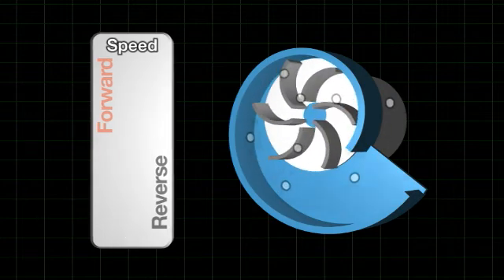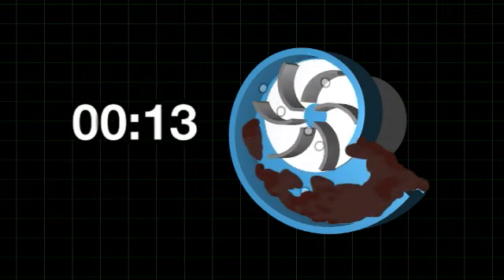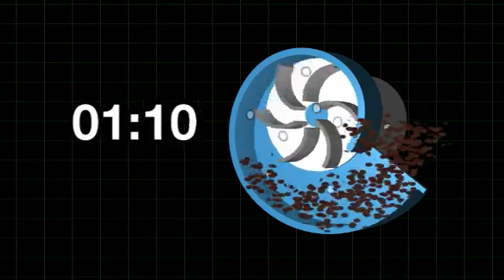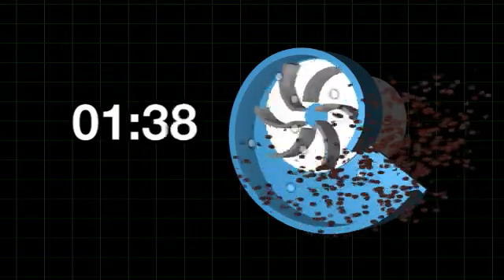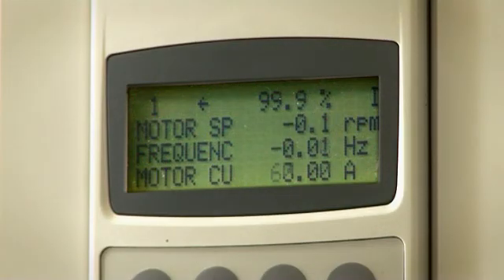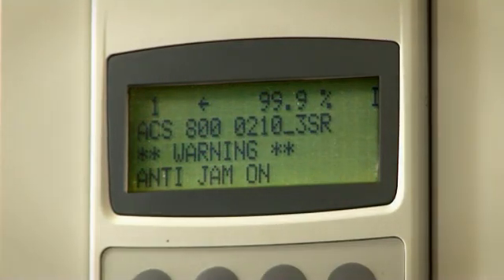Taking one to two minutes to complete, the cleaning cycle removes the debris from around the pump volute, preventing it from entering the pump and blocking it when the pump ramps up from zero to its normal operating speed. The cleaning cycle is also started when the variable speed drive detects a drop in pump efficiency.